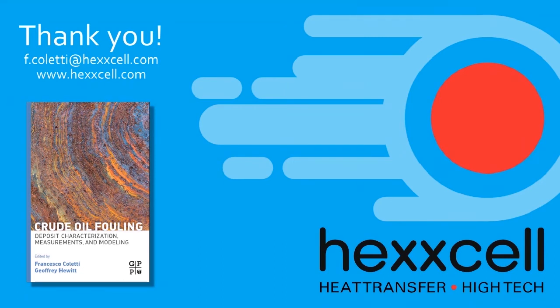I understand. Thank you very much. You talked obviously about AI and the digital twin. Could you expand a bit on what kind of typical data you do need in order to set up that digital twin? Well, digital twins, the answer is the more the merrier. The more data we have, the merrier. But we have learned to use very little amount of data. So we use data readily available from typically refineries or other plants, which are temperatures, flow rates, and pressure drops when these are available. If we want to also look at the fluids, we need to have information on the fluids, how the fluids affect fouling. We can do that, but we need to have information on the type of fluids or the type of crudes that have been processed in the refinery, which are not always available, but in most cases they are.